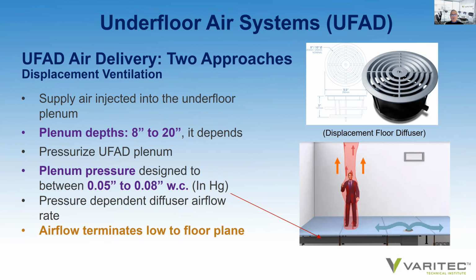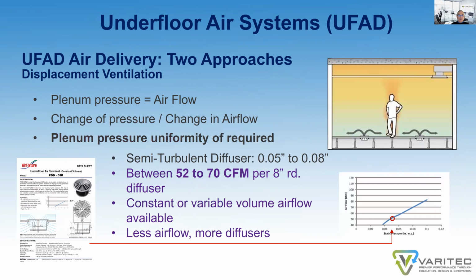So what about a displacement ventilation solution? Supply air is injected into the underfloor plenum. Plenum depths can be designed at 8 inches to 20 inches. Again, all the properties of the semi-turbulent underfloor plenum apply, uniformity of pressure. However, the air is discharged through a different type of diffuser face, low to the ground at lower velocity to allow for full thermal stratification throughout the cubic volume of space. These diffusers at 0.05 to 0.08 inches can supply 52 to 70 CFM through an 8-inch round device. These devices too can come in a 10-inch size.